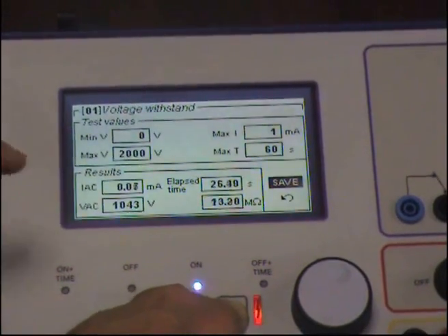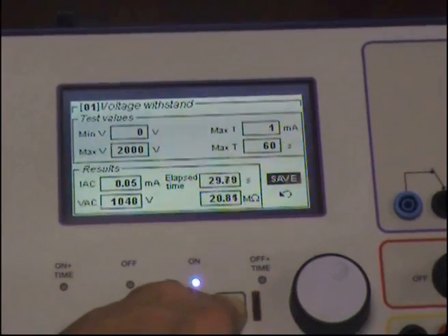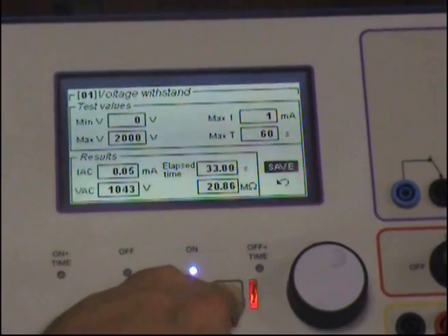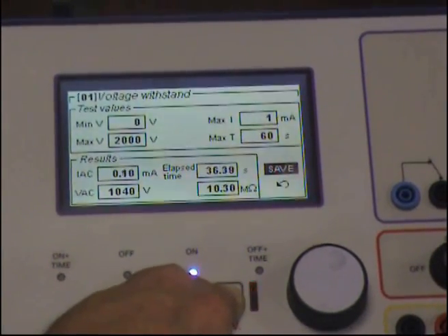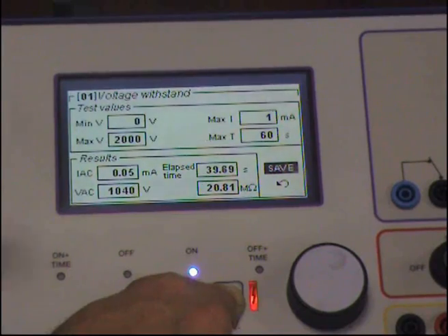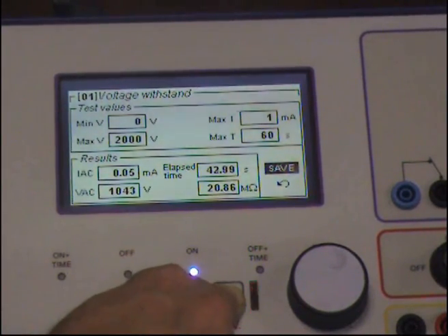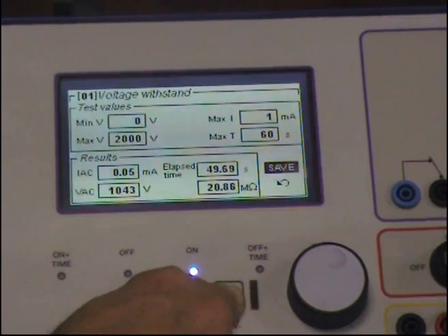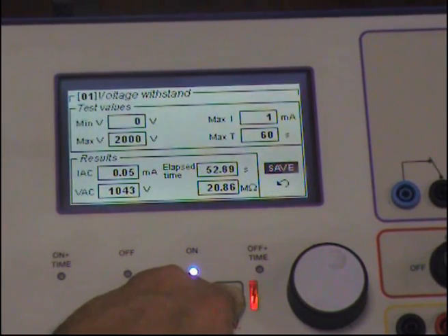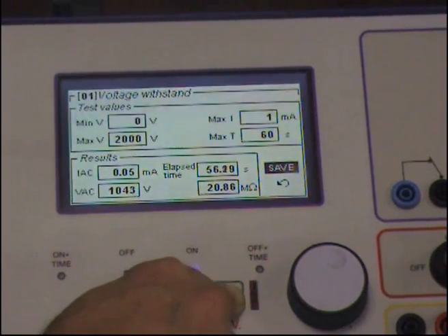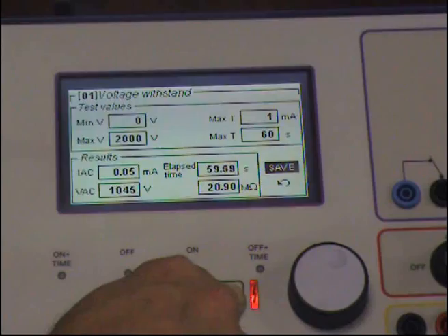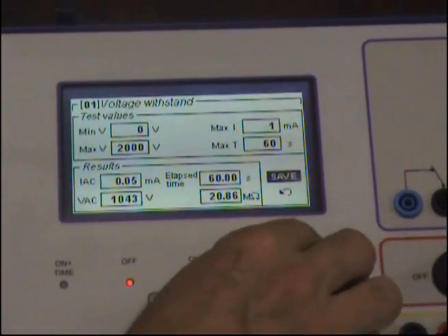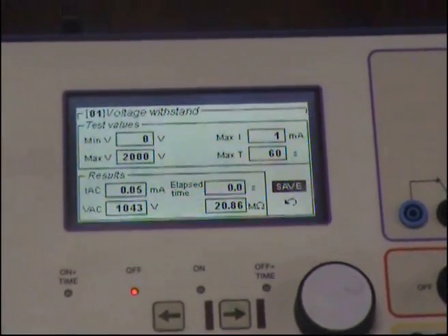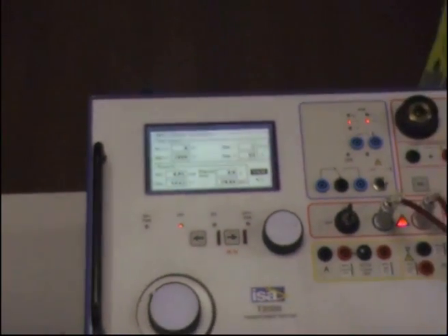Okay. During this test I can see here the isolation impedance, in this case because I am applying an AC voltage. You see the item is withstanding the test. I have this elapsed time that is going on. As soon as I go to 60 seconds, the test will be terminated. Okay? You see? And that's it. Now I can go to save. And this is it. Of course you can do the test up to 2000 or 3000 volts as you like.